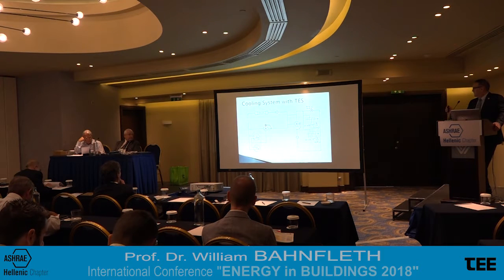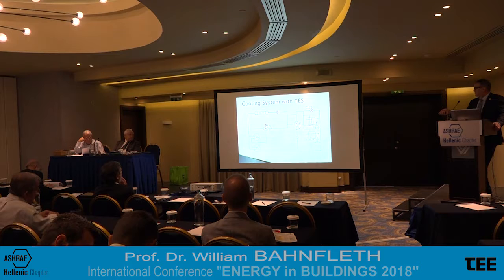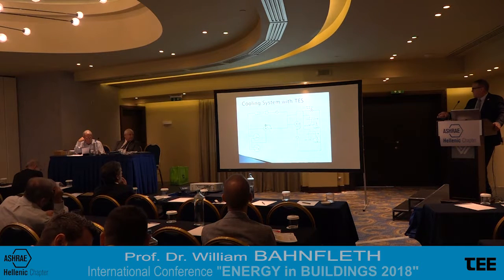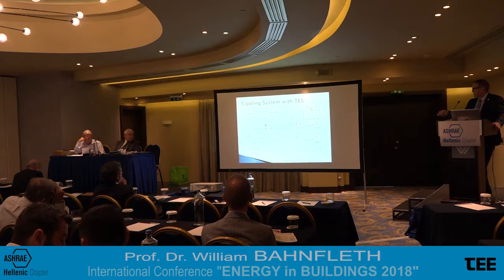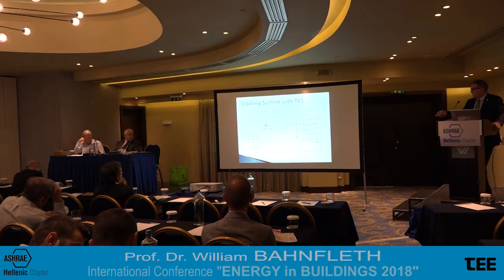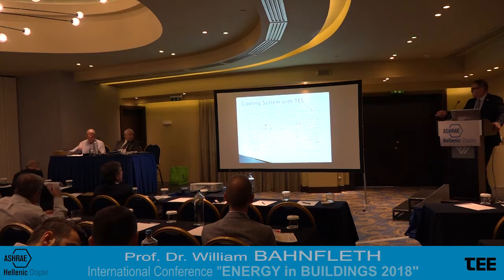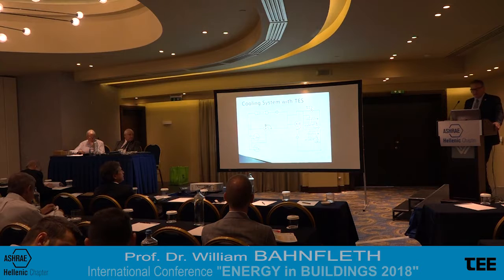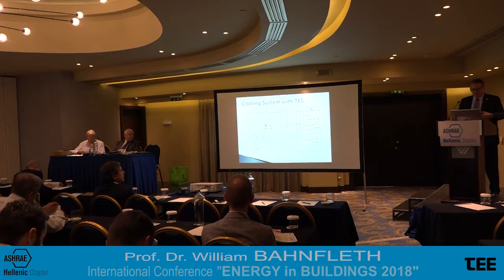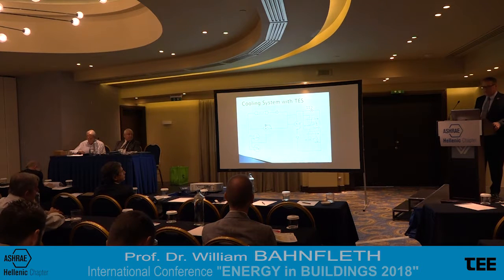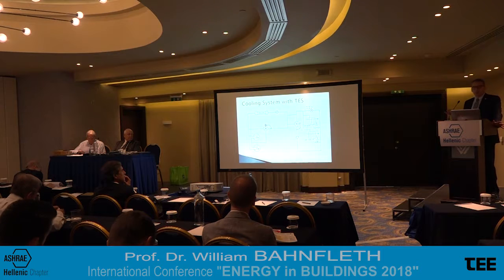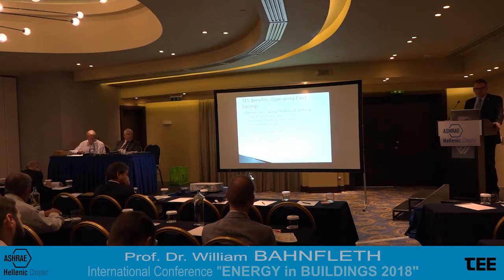In a system with thermal storage, such as the small ice storage system shown here, we have the ability, there it is, there's a pointer, to meet cooling load directly from the chiller with no storage. The chiller could be off and we could be providing capacity entirely from storage, or we could be blending water that's partially cooled by the chiller with water that's diverted through the storage to meet the load. So there are many different configurations here that, to some people's thinking, add complexity; to other people's thinking, they add flexibility and the ability to do more and better things with the system.